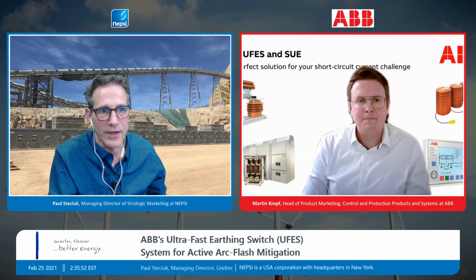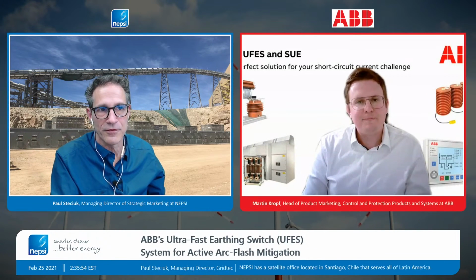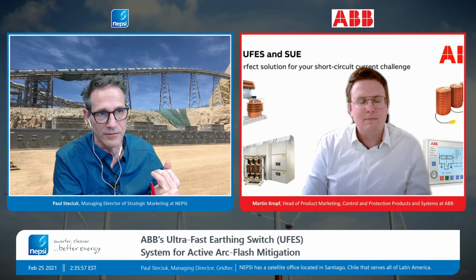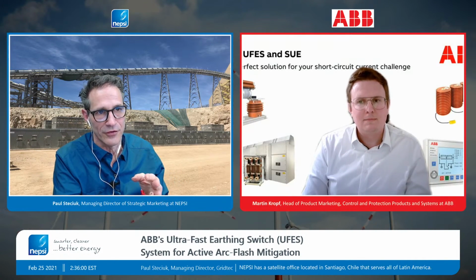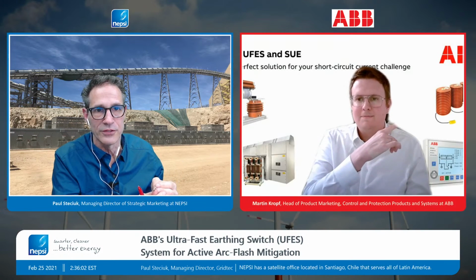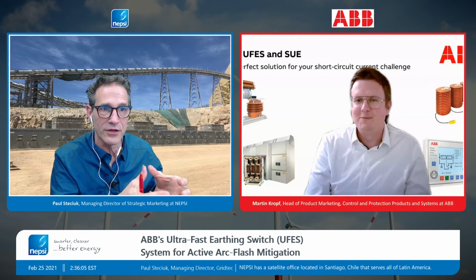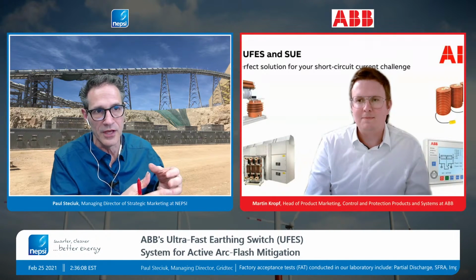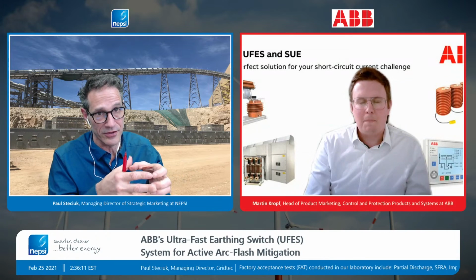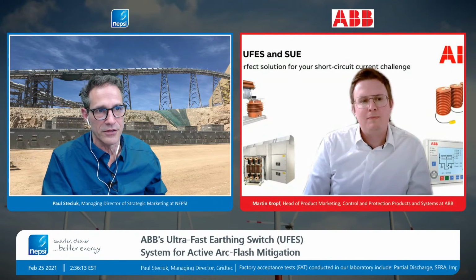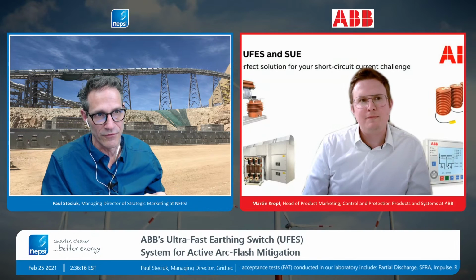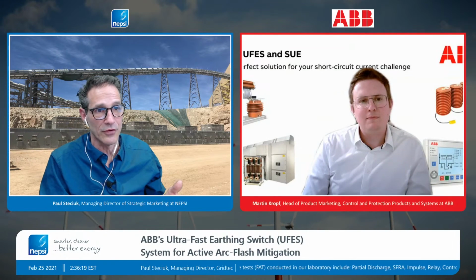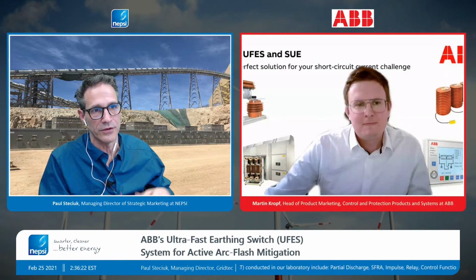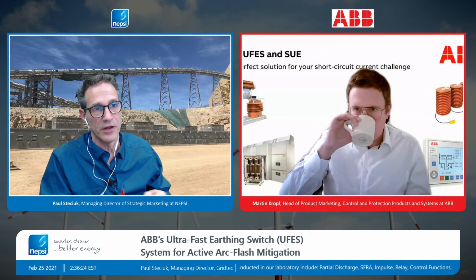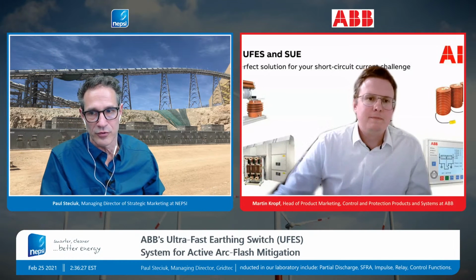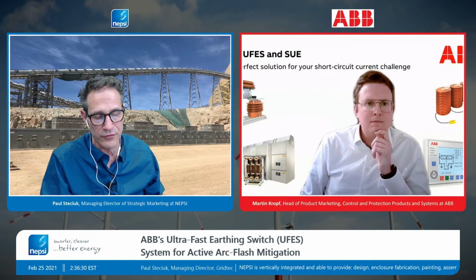So I might add a little bit to your answer. First, it's a very easy device to install. To the right of Martin are the three power switching elements. They install in a very tight area. In fact, they can replace a bus support insulator. They're that small. So as a retrofit option it is very easy to install. You have to install a relay in the panel somewhere, cut out the panel, install, put a transfer trip in, and run the fiber optics. But all very well possible by a company that's a panel builder, for instance.